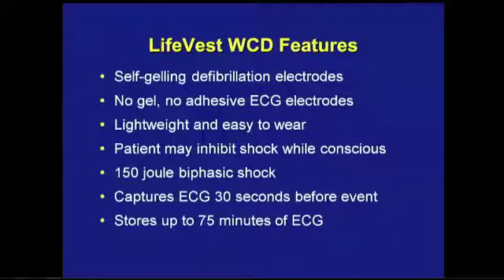The way this device works is it has self-gelling electrodes that deploy. There are no electrodes that need to be stuck on. It's lightweight, easy to wear. The patient is able to inhibit a shock by pressing a response button on the belt of the device if they remain awake. It delivers 150 joule shocks, captures 30 seconds of the electrocardiogram before the event, and can store up to 75 minutes of electrocardiographic recording. So this is where the device can actually work for risk stratification, to look for sustained but spontaneously terminating ventricular arrhythmias, for example, during the waiting period.